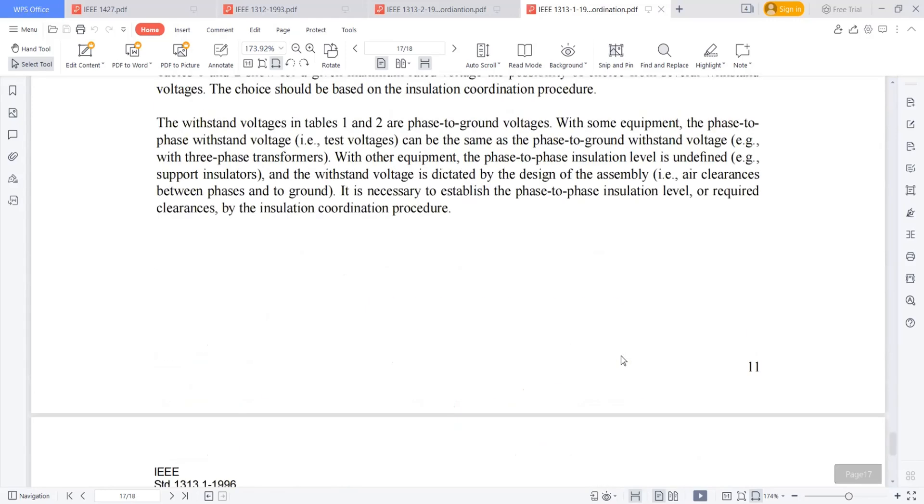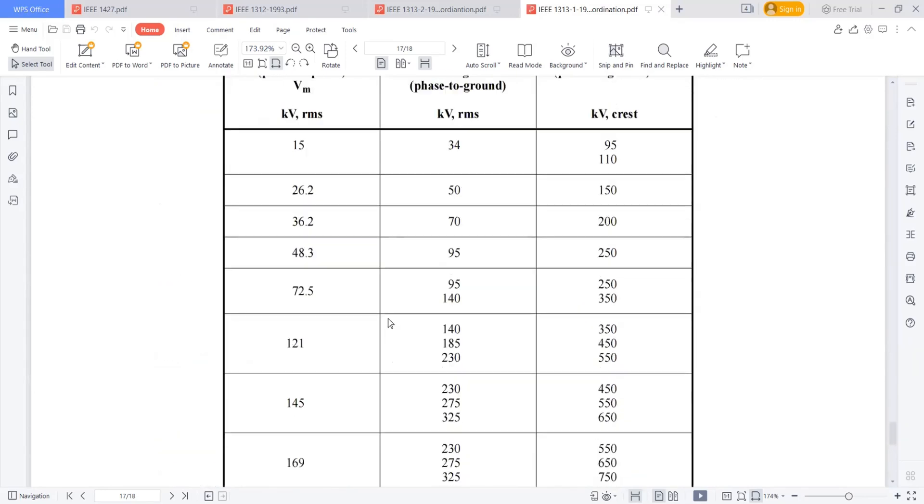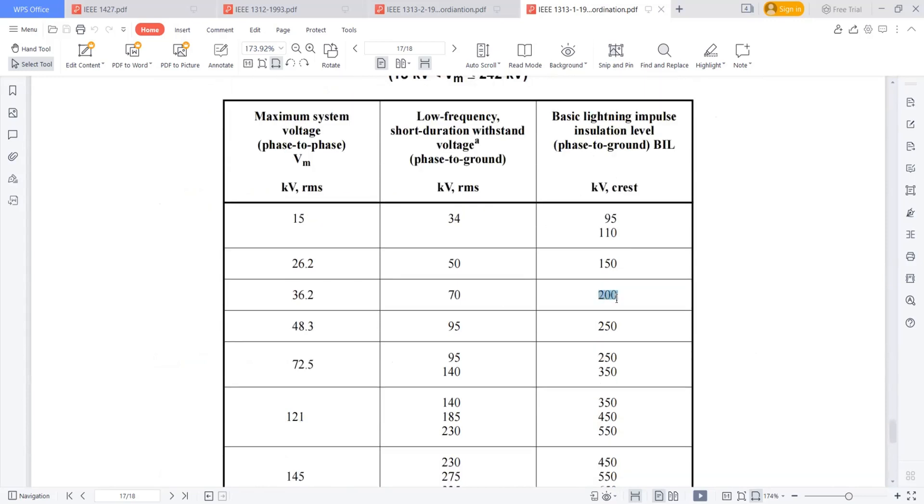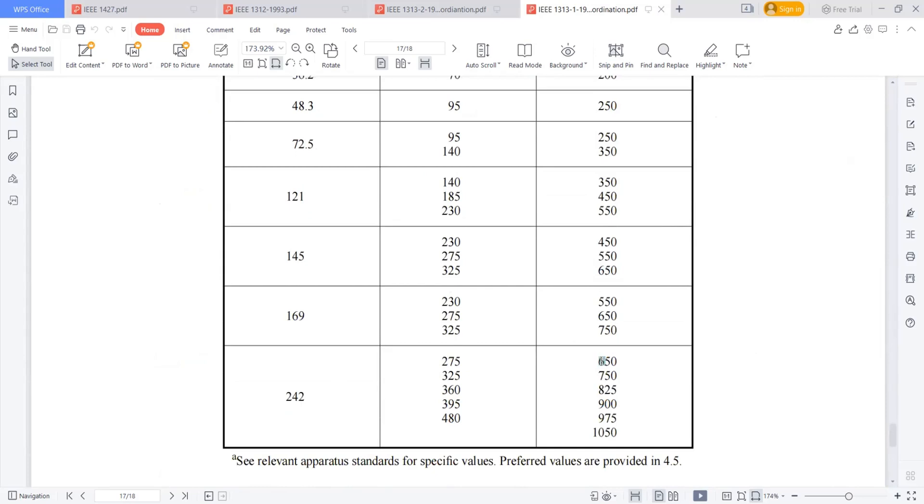It is a standard kind of thing. Suppose if mine is 33 kV, the BIL level is 200 kVp, and the low frequency short duration withstand voltage is 70 kVp. And for 220 kV, these are the values you can see.